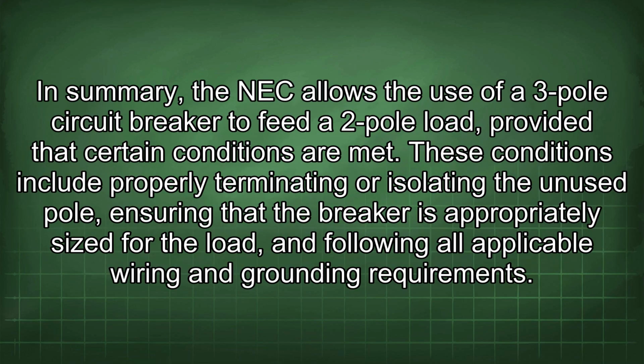In summary, the NEC allows the use of a 3-pole circuit breaker to feed a 2-pole load, provided that certain conditions are met. These conditions include properly terminating or isolating the unused pole, ensuring that the breaker is appropriately sized for the load, and following all applicable wiring and grounding requirements.